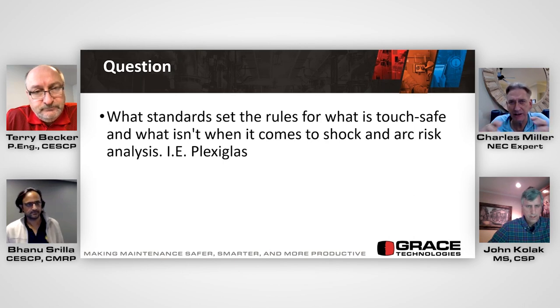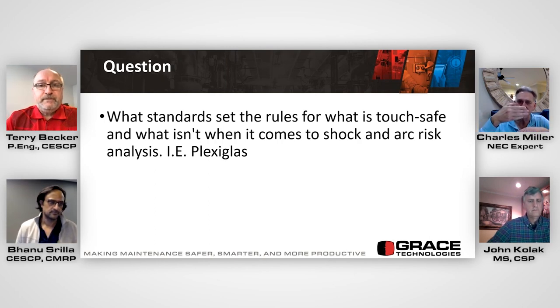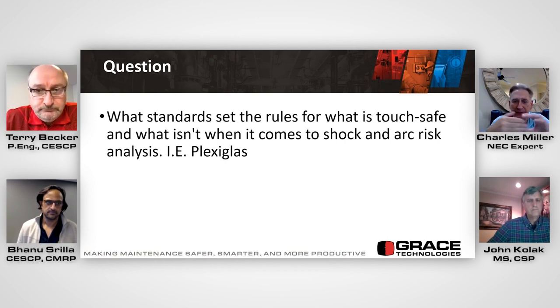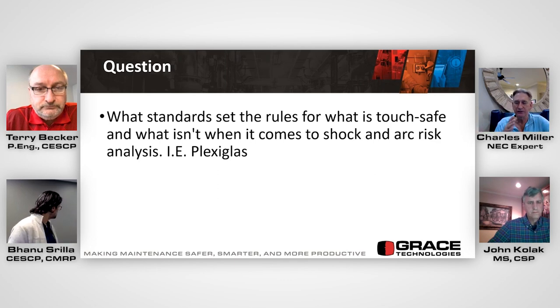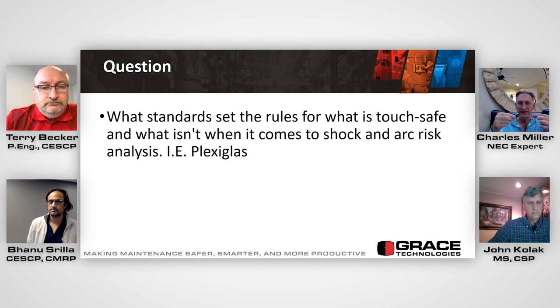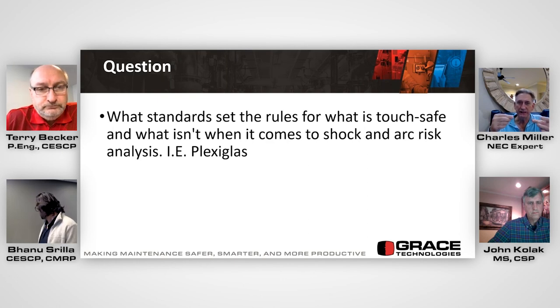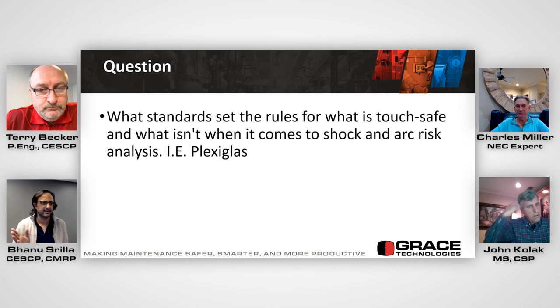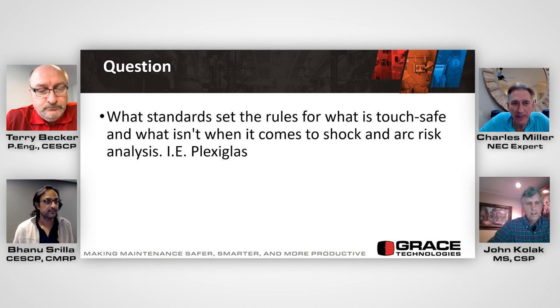Sometimes customers and clients think, well, it's got a little piece of plastic above the lugs, some red plastic or whatever color, and that's finger safe or touch safe. Well, no - if you can reach your finger in behind it, that's just a little plastic guard, not finger safe or touch safe. Terry's right, it needs to be explained by the manufacturer when something is finger safe and touch safe. The plexiglass just provides a barrier, it doesn't provide finger safety. That's the differentiation between a dead front and a live front.